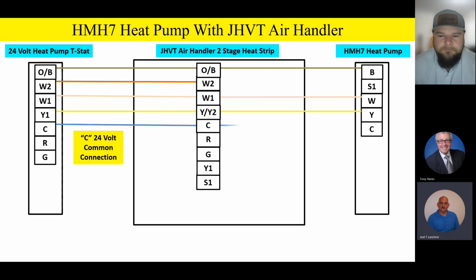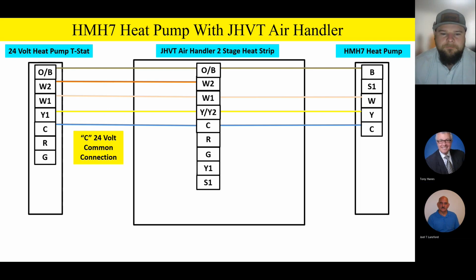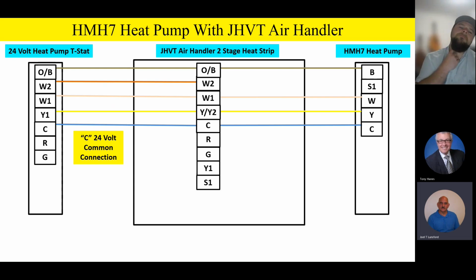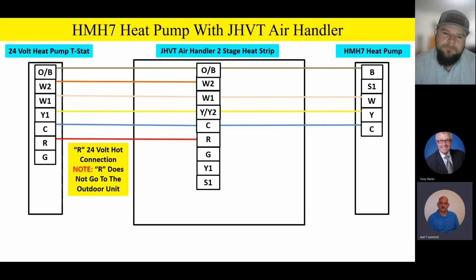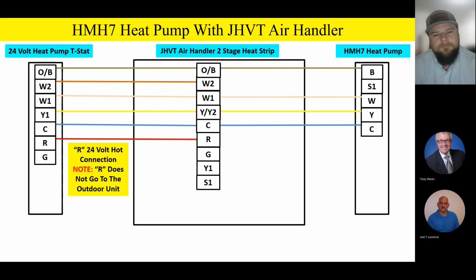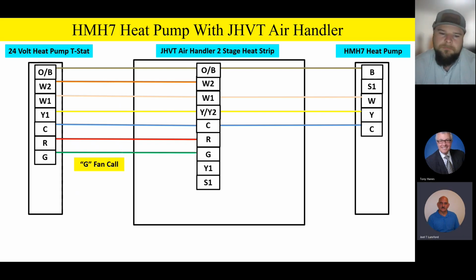C terminal goes all the way through. And please remember one more time that C terminal going all the way through is a hard wire. We want to make sure we've got that hard wired common terminal going all the way through. Our 24 volt hot is going to go to the thermostat and to the indoor unit, but it does not go outside. That's important to remember. And then the G terminal is your fan call, G to G.